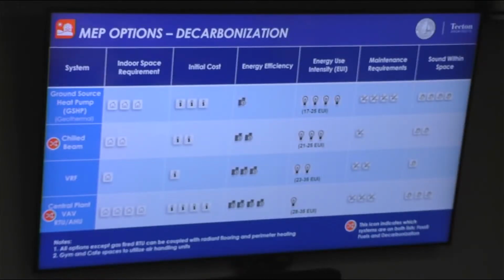So for MEP options, decarbonization and all-electric are very similar—chilled beam with a central plant, VAV, rooftop or indoor air handler. We can also do a few other things, all using geothermal wells with a ground source heat pump, which is actually the most efficient. But one big issue is that it requires a lot of space within the building, since you have decentralized equipment throughout requiring closets and such, which takes up usable floor space that could go to other programs. It's a great, efficient system at a relatively good cost, but it affects your overall building square footage and program.